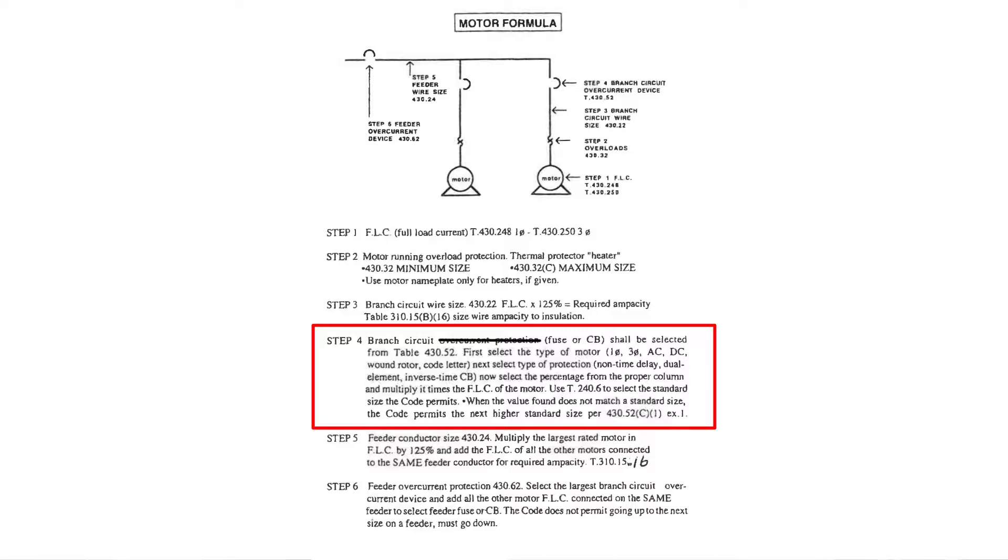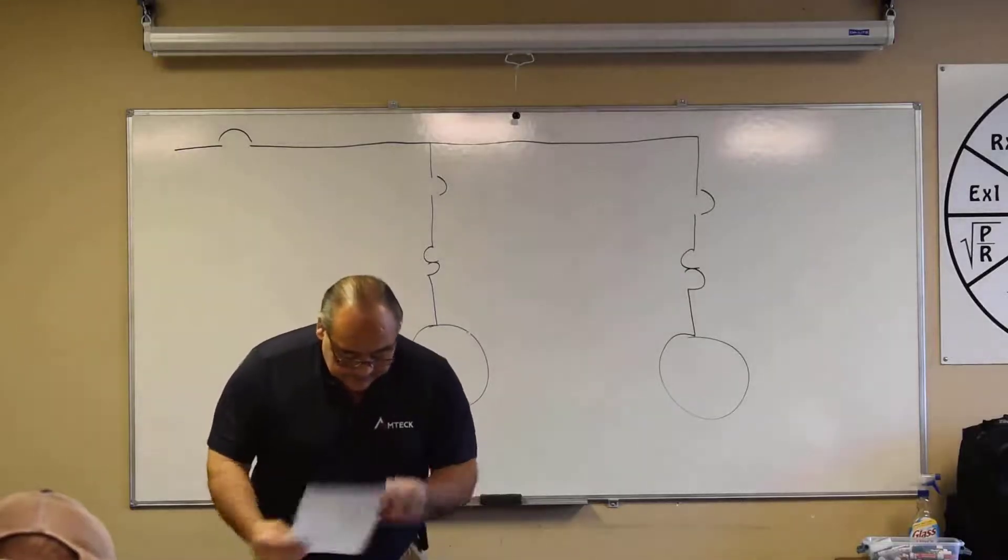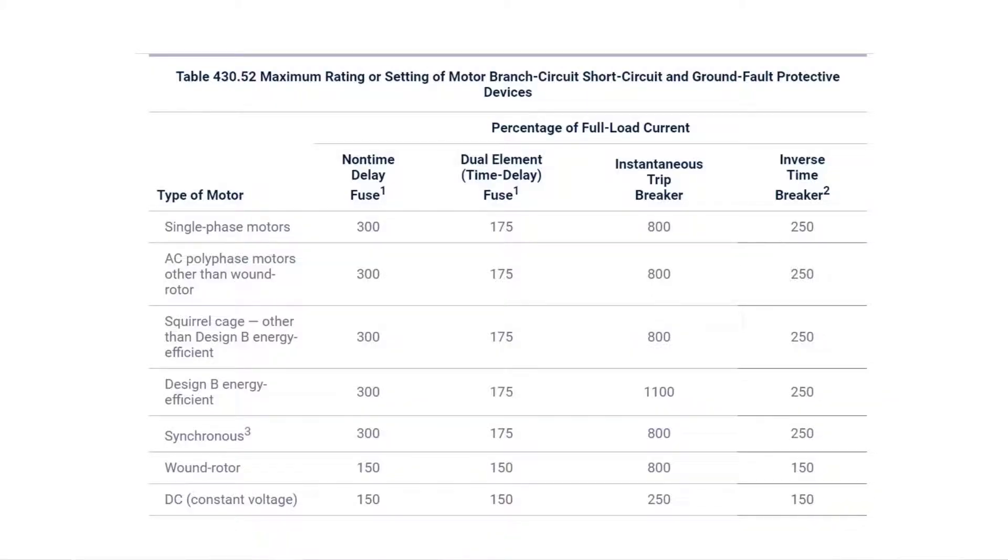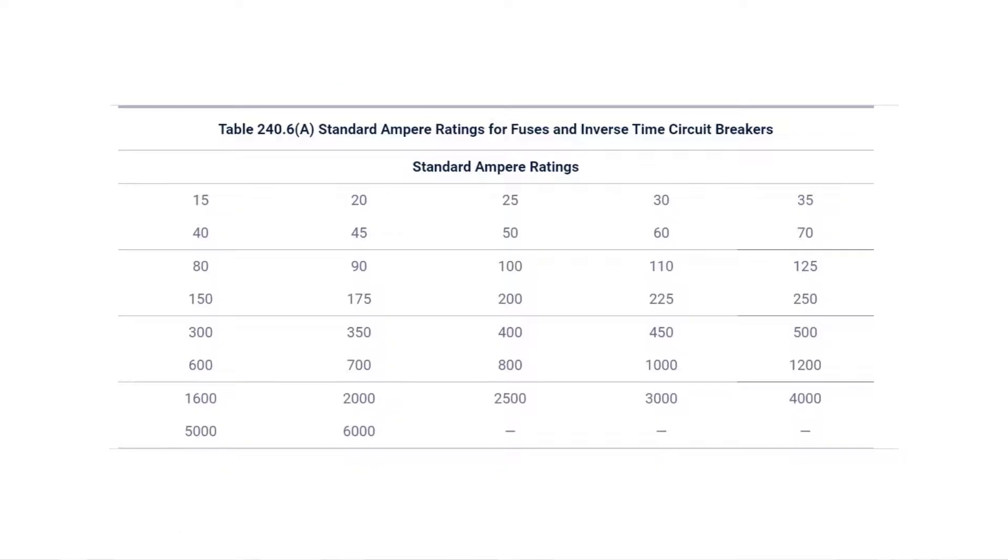When the value found does not match the standard size, the code permits the next higher standard size. So let's use this 10 amp motor at 240 volts, single phase. Now we're going to size the fuse or circuit breaker on step number four. Hold the page with a piece of paper and let's go to that table 430.52. Got something glued in right beside it, right? Conveniently. That's that 240.6 table, the standard fuse or circuit breaker sizes.